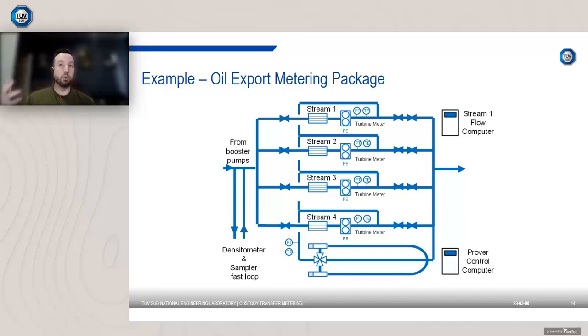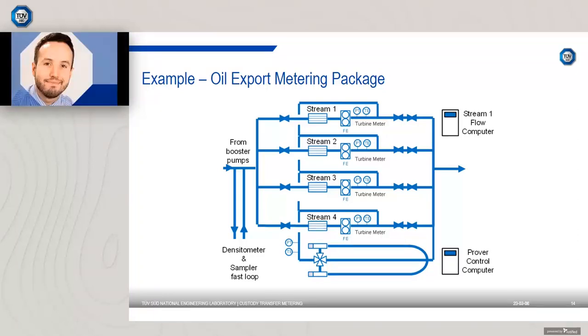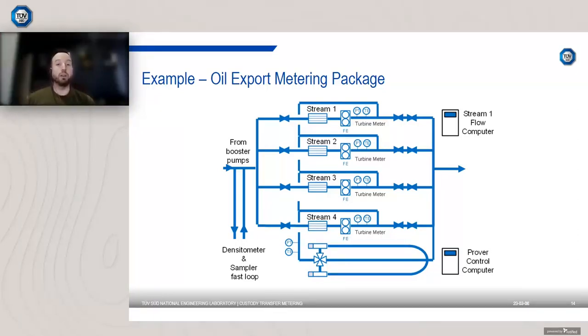Now, obviously, this is a multi-stream system. So we talked about turndown. Turndown usually governs how many streams you've got. It's often quite difficult to get a single flow meter to meter both the minimum and the maximum flow within the uncertainty. So you wrap the meters together in parallel, and that allows you to maintain the accuracy that you require. When you're metering small flow rates, you can turn off maybe 1 or 2 streams, and you can still maintain that accuracy and those uncertainty targets.